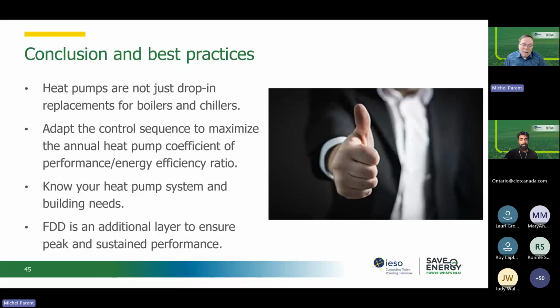And if, for example, that limits your ability to do hybrid operation, you would need to either install new points to control that, which would be expensive, or just not select that product because you need to be able to do that fine tuning to get the most out of it. So either they unlock those points for you, or you go to a different manufacturer, or you can actually take over the control. But there's a significant additional cost to that.